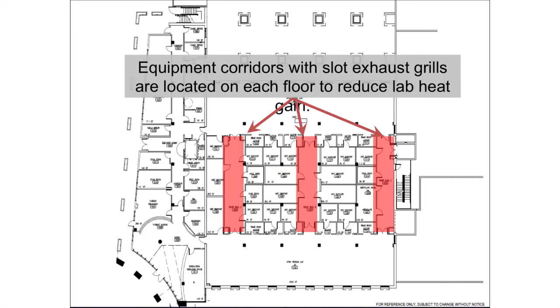We saw earlier where I had it laid out with green blocks, and then we looked at the lighting. These are your big open lab bays, and we have these equipment corridors. They're shared equipment corridors where we ask all of the ultra-low temp freezers, all the incubators and those kinds of things to be stored, so that we don't transmit that heat gain out to those open lab bays. They're designed this way. They're fire marshal and exiting approved. They have magnetic hold opens on the doors so that people who are gloved up don't have to open doors to get to these corridors. These are well thought out and well designed spaces.